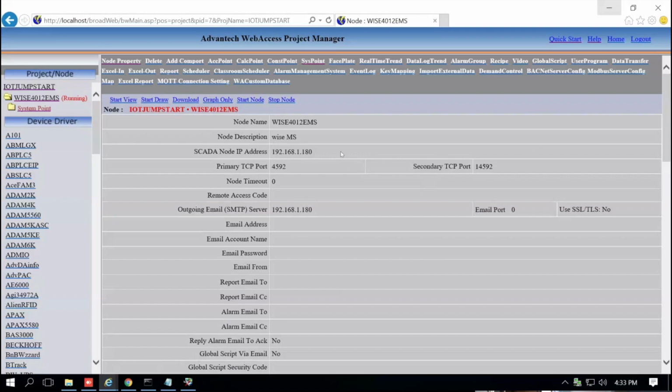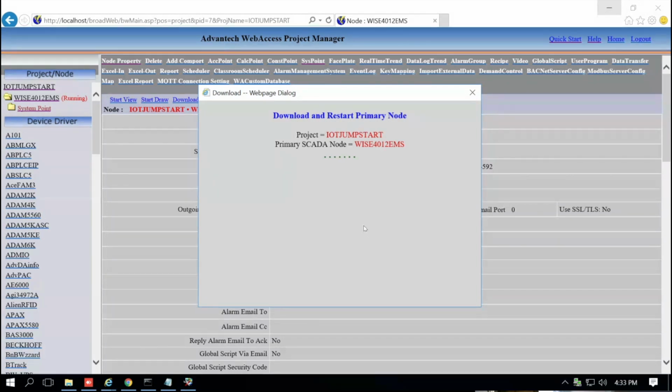Okay, so from here, I have changed the setting on the SCADA side. Let me download and re-trigger the whole setup again. As you can see, when you are dealing with so many details, sometimes you might forget a few steps or where to set up. So this is how we can troubleshoot in case you encounter the same situation where you don't see any data in terms of logging. Do go and check whether you have the data logging enabled. You can cross-check on that portion.